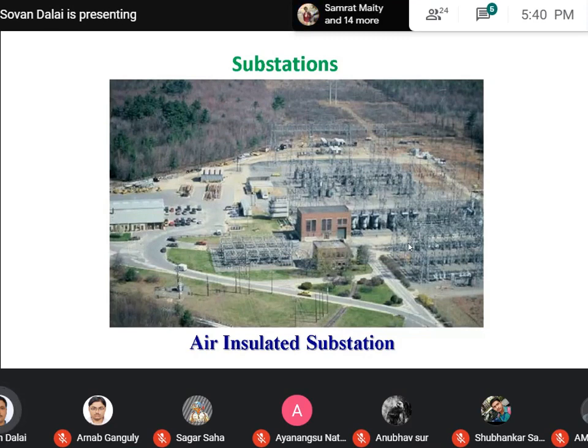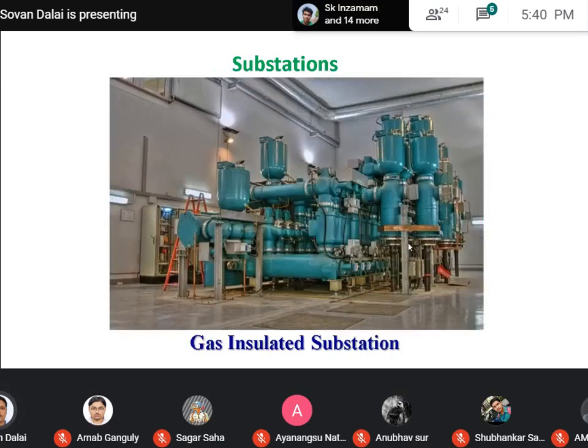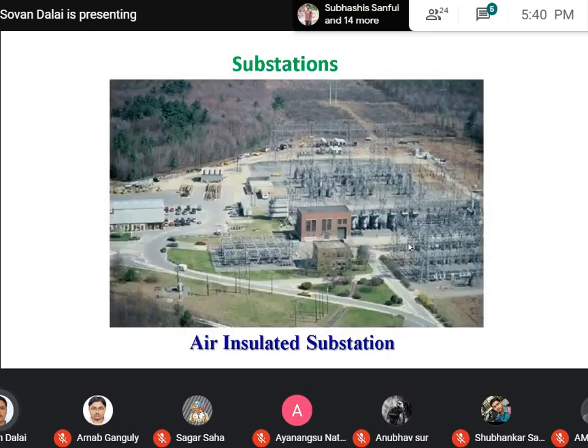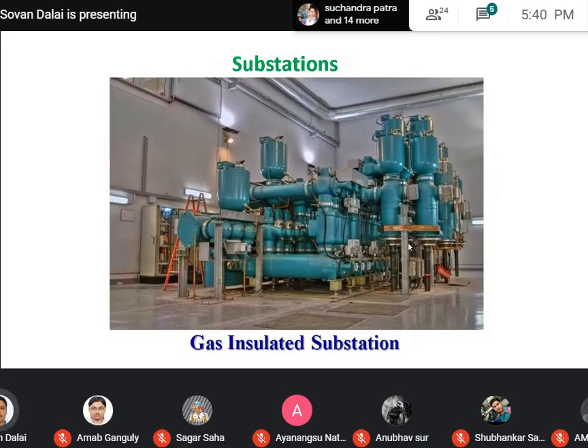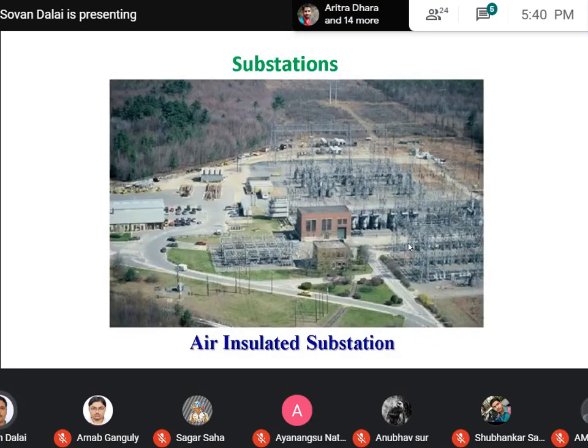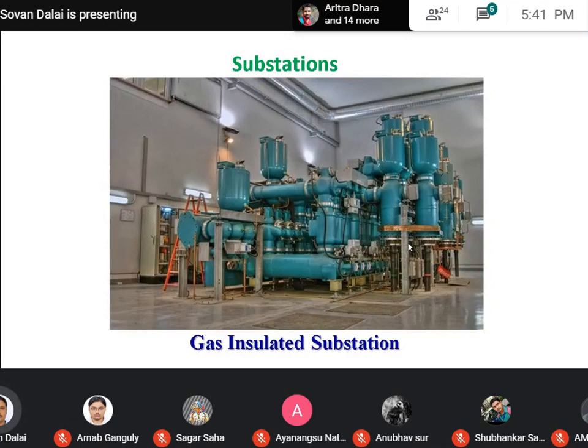This is one example of an air insulated substation, where the insulation is provided by the air. And nowadays, due to the shortage of space, we are going for gas insulated substations. If you require, say, a 200 meter by 200 meter place for an air insulated substation, in the case of a gas insulated substation only one big room is sufficient to hold a similar voltage level.